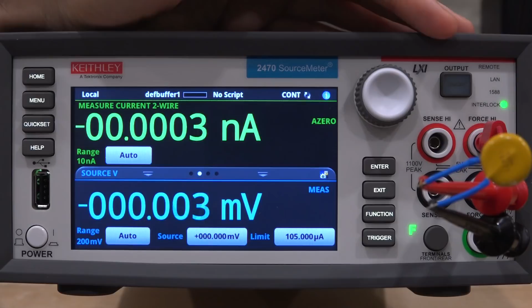So here's a varistor, directly connected to the output of the SMU, and we're going to do a sweep to find out its IV characteristics. A varistor is essentially like a diode, but in both directions, so we should be able to use the multi-quadrant feature to characterize it. At the same time, these varistors have very high voltage responses, as expected — they are protection devices after all — so you cannot measure them using traditional SMUs. You need something that goes to high voltages.